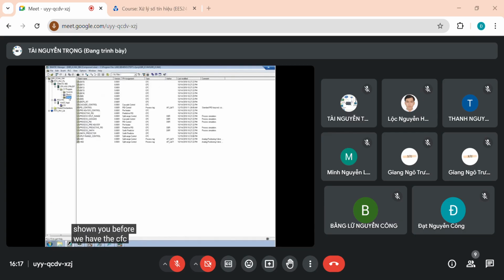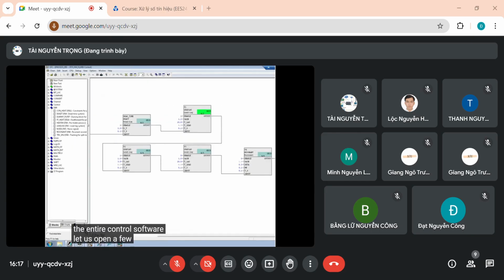Here you have the CFC chart folder. CFC stands for Continuous Function Charts, and CFC is a graph editor that allows you to program the entire control software. Let us open a few charts. What you see over here is a chart that allows you to implement a process. Remember here that we use PLC sim, so we do not have any actual system. So what we'll do is simulate the system, emulate the system, and you can see that we can do this very easily using this graphical editor.